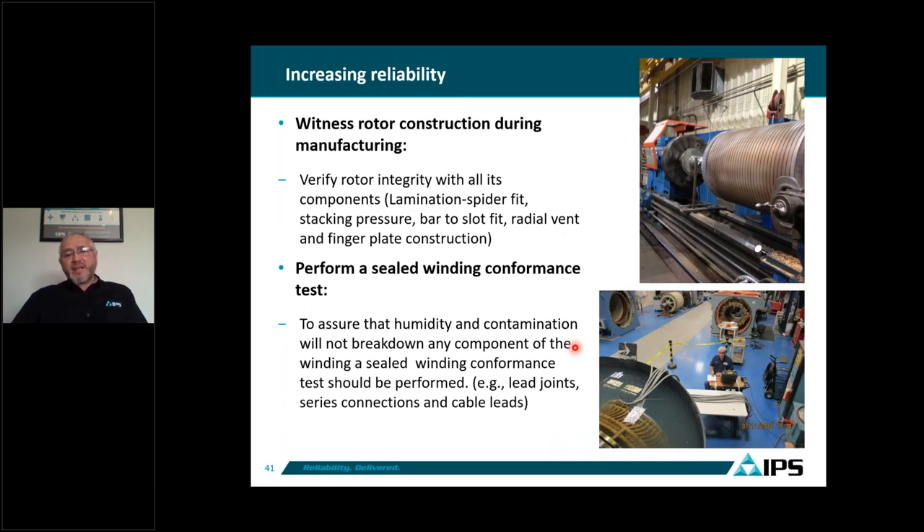Another way to increase reliability: when I was with OEMs, we always paid attention to the stator, and in API there are many hold points and inspections during stator manufacturing. But very little attention is paid to the rotor. It is important to pay attention to the rotor — look at the integrity of all components: the laminations, spider fit, stacking, bar slot fit, radial vent, and end fingers — make sure you have a robust motor, and question the OEM about these elements.